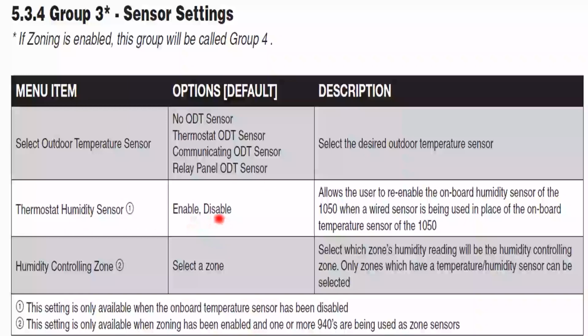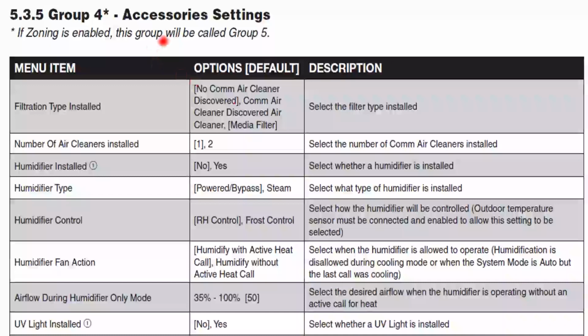Humidity sensor, you can enable or disable. Humidity controlling, select the zone. Group 4, accessory settings. So we always want to go and tell it what filtration type is installed. Do we have a communicating air cleaner? If it is communicating, it should pick it up right away. Do we have a media filter? Number of air cleaners installed. So if you're doing a double side tap and you have 2 air cleaners, you'll change that to 2. And then humidifier installation, humidifier fan action.